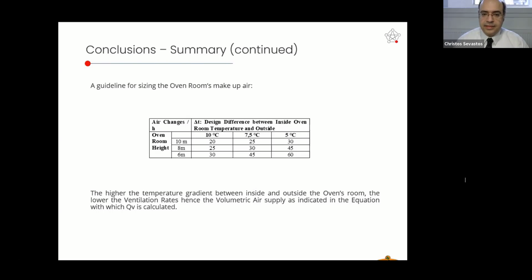10 degrees, 10 meters high room, 20 air changes per hour. 7.5 degrees temperature difference between room temperature and outside temperature, 10 meters high, 25. 8 meters high, 30. 6 meters height, 45. The higher, as we have said, the temperature gradient between inside and outside the oven room, the lower would be the ventilation rates, hence the volumetric air supply, as indicated in the equation to which we have been referring in the previous slides.